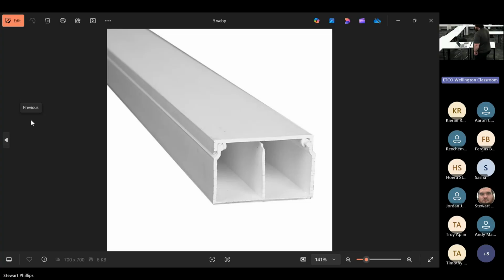Yeah, so one unfortunate thing of my apprenticeship, because I did Housing New Zealand work, carried up 10 floors like that. When I did Housing New Zealand work, when we first started, they would not let us cut holes and patches. So sometimes when we had downstairs, upstairs split units, the downstairs flat would have its stove upgraded from gas to electric, which means I had to run a 6mm twin and earth cable to the stove location from the switchboard. And sometimes that switchboard was in the hallway, so I'd have to come down the hallway, through the kitchen, along the full length of the kitchen and around the corner, and then down to the stove.